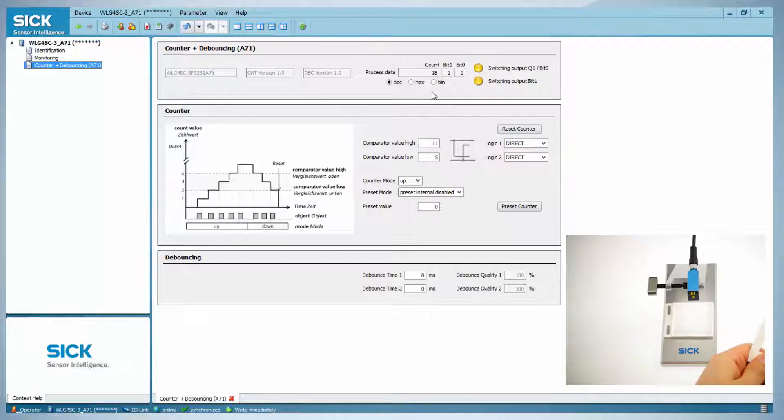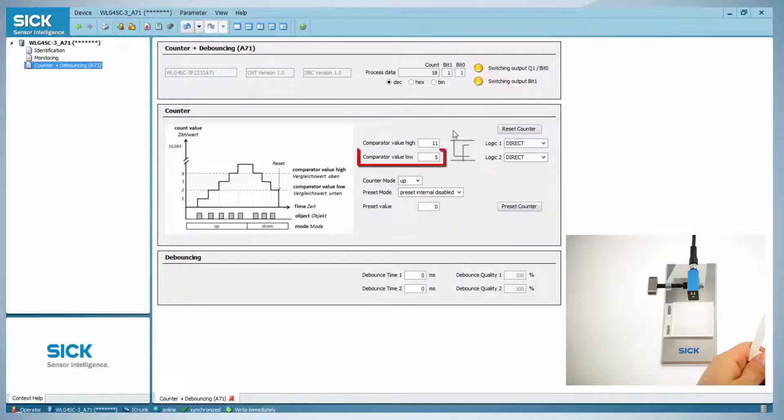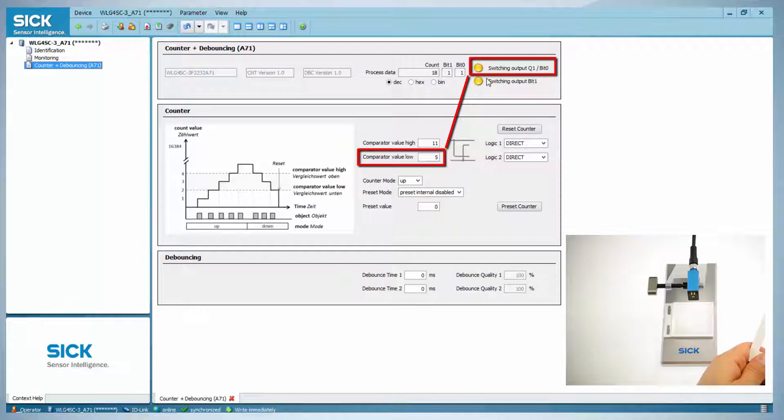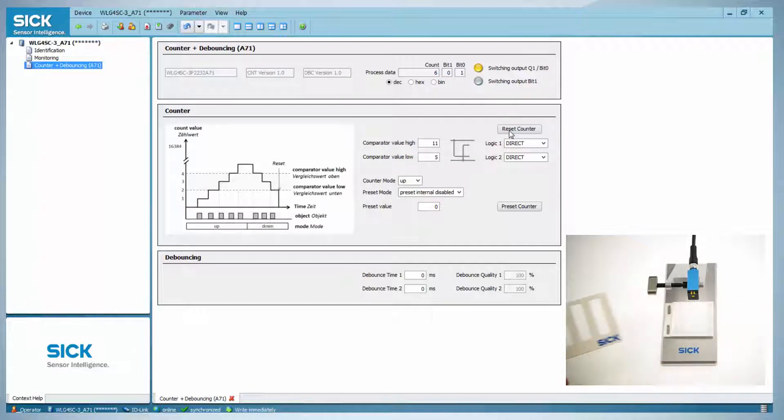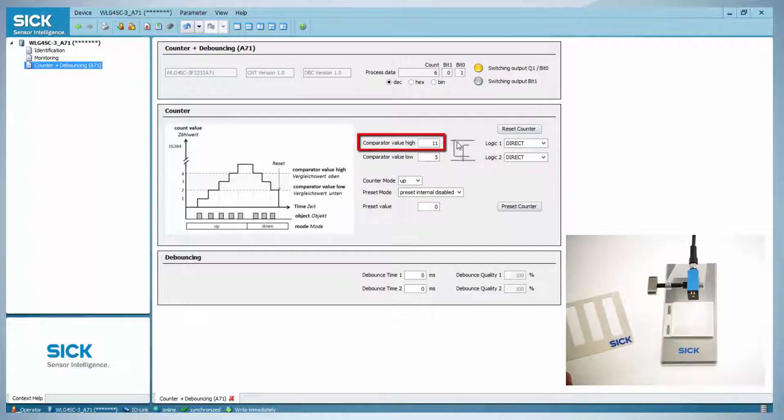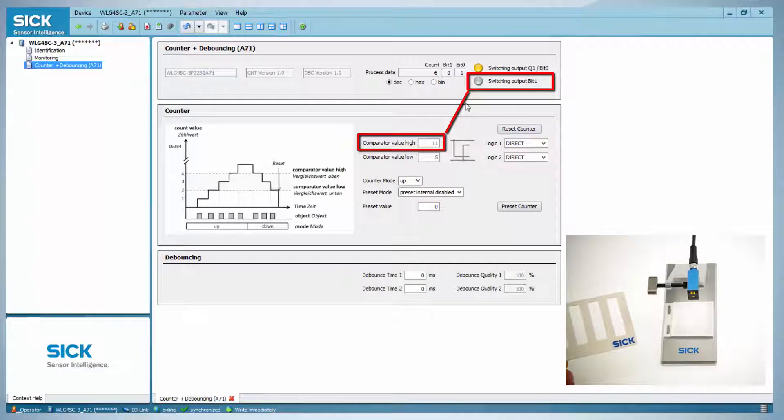The sensor reliably counts the bars. The sensor currently has the following settings: the comparator value low is set to five, so the switching output Q1 is triggered as soon as this value is exceeded. If the counter is reset by clicking on reset counter and then the object is moved slowly, the output is activated on the sixth bar. The comparator value high is set to 11, so the output on bit one is high as soon as this value is exceeded.